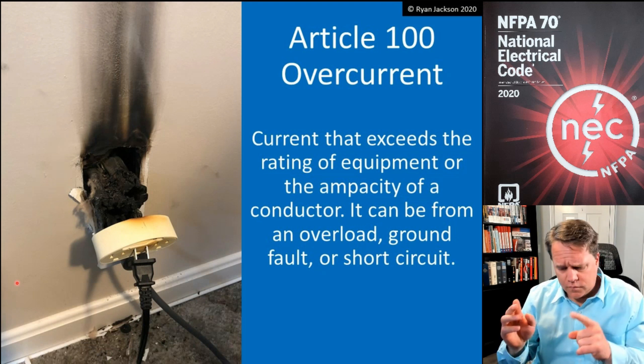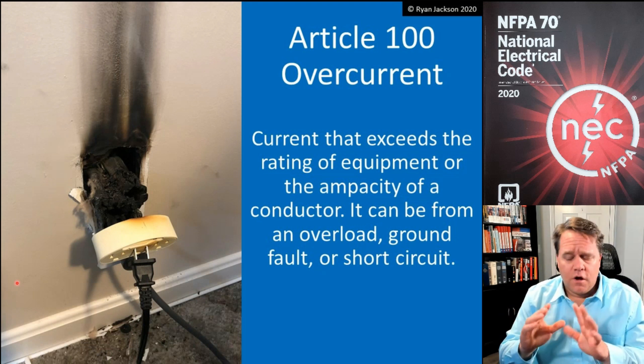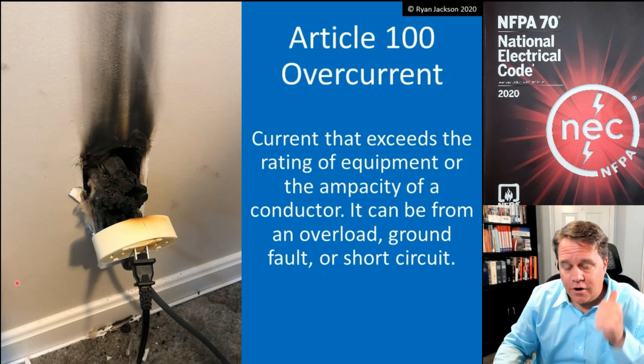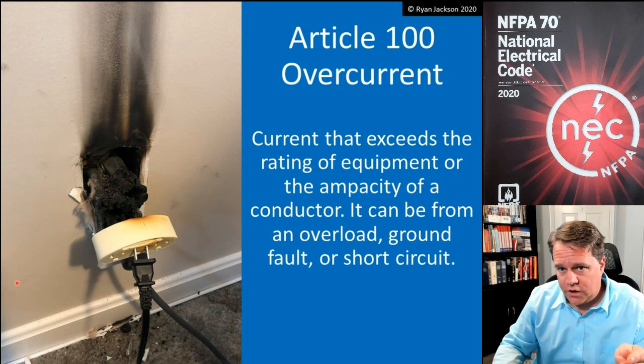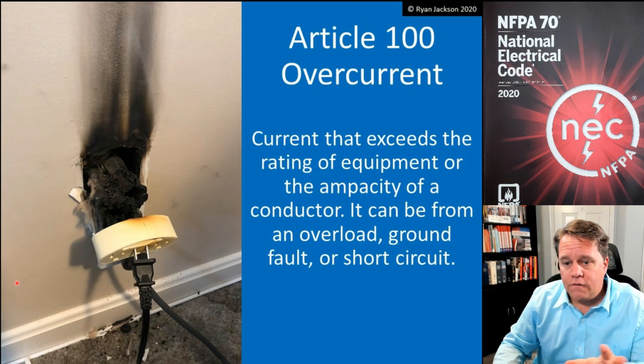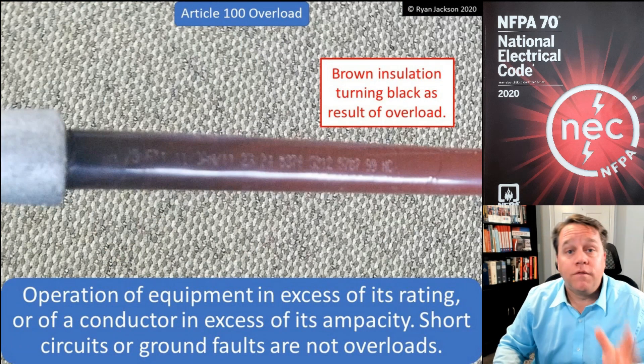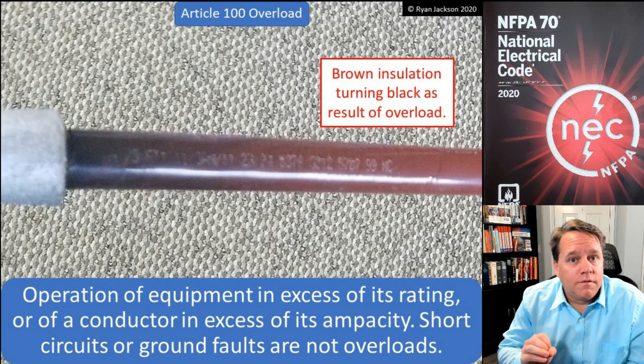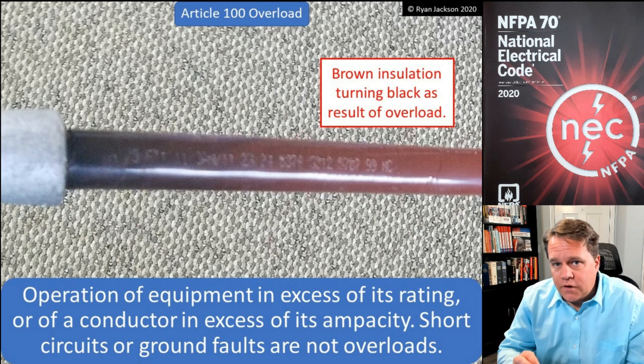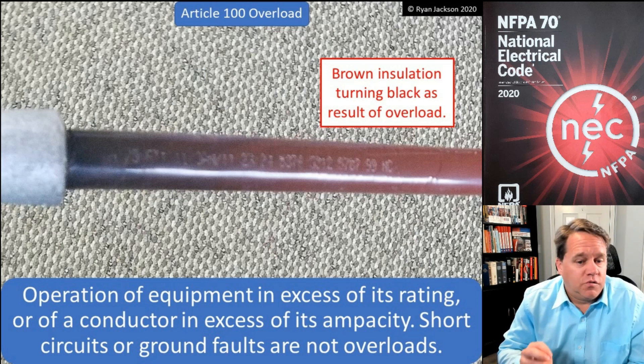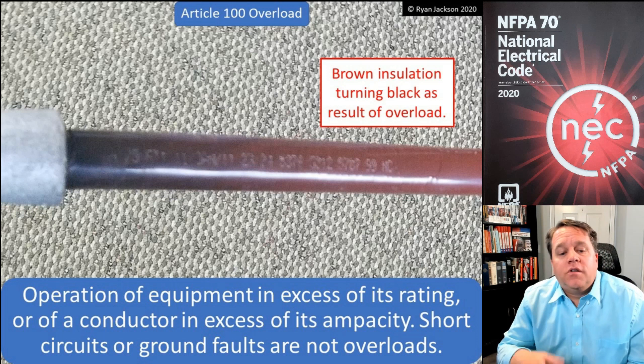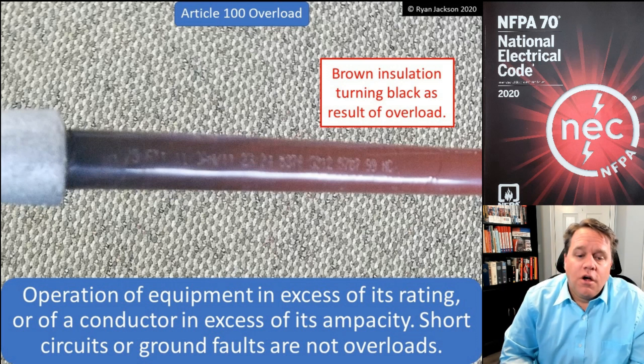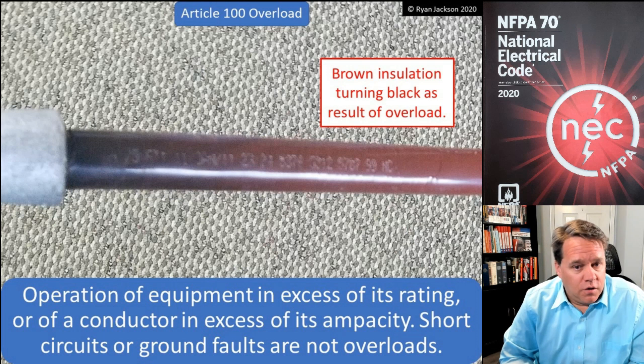So overcurrent is current in excess of the conductor's ampacity or the equipment's rating, resulting from an overload, ground fault, or short circuit. Now, an overload is defined in Article 100 as operation of equipment in excess of its rating or operation of a conductor in excess of its ampacity. Short circuits and ground faults are not overloads.